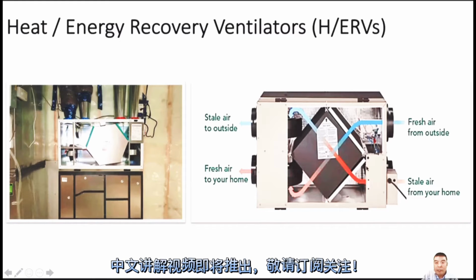The filter normally needs to be cleaned every three months. Check the filter, and if it's dirty, you need to service it. The heat exchanger we can pull out too. Normally, once a year, I recommend the customer clean it in the summertime. Just bring it outside and wash it with a garden hose. After washing, dry the heat exchanger and then put it back. In wintertime, if you wash it, don't put it back directly. It must be dried enough, otherwise if there's water inside and it freezes, it will crack and break the heat exchanger.